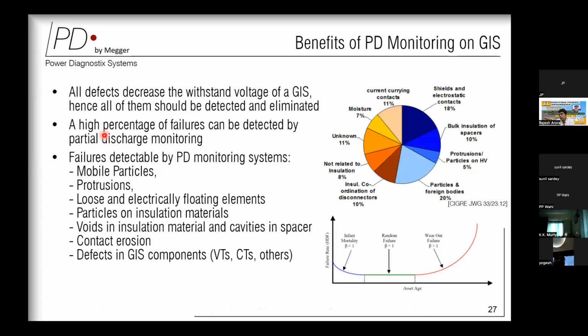So when we do all these tests, now the question comes, what kind of information will this give you when you do this PRPD measurement? All this defect decreases the withstand voltage of GIS. Whenever the PD occurs, they will basically reduce the withstand voltage of a GIS, and a high percentage of failure can be detected when we do this partial discharge monitoring. So if there are about 10 types of errors or malfunctions which are happening in GIS, all of them will contribute to some partial discharge or some discharge phenomenon, and they all can be monitored if we are doing a watch onto this partial discharge voltages.